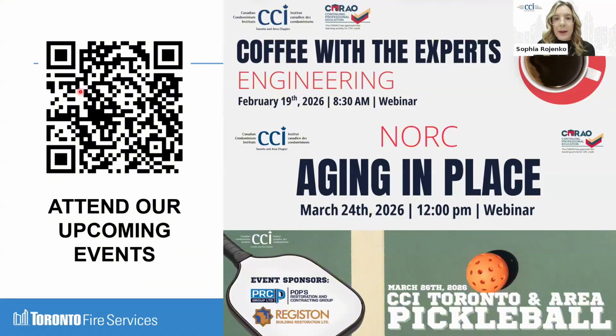So a similar question with respect to fan coils. Please clarify if we need CO detection for suites with heat pumps inside the unit. So again, hydronic type equipment. It's case by case basis. I know that's not the answer you want, but if you have a heating coil and the supply is coming directly from the outside, there's no natural gas involved whatsoever in that process. The liquid is heated remotely from another part of the building. You may not need carbon monoxide alarms, but for me to give you a conclusive answer, I would want to see the actual specifications of the equipment and the overall HVAC plans. So this is what you have to do. If you have any doubt, go to the building division, get the HVAC plans, because you have to assess this on a case by case basis. Is it possible to get CO blowing through that fan? That's the question.